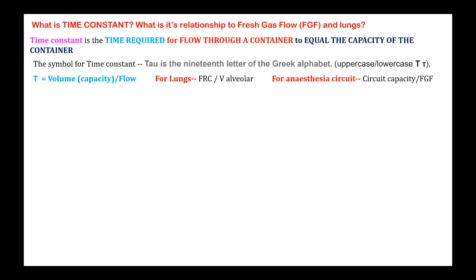So how does the concentration in the breathing circuit rise? If you want to increase the concentration of the anesthetic agent in the breathing circuit, what are all the things that you can do? Set dial concentration of the inhaled anesthetic. Increase the dial concentration. Higher dial concentration, then will keeping the higher dial concentration alone be enough? You have to give a fresh gas flow.